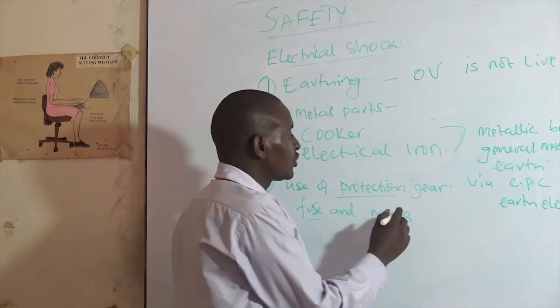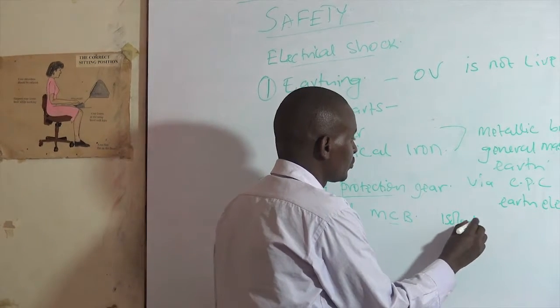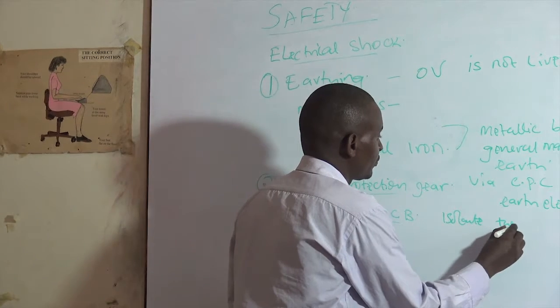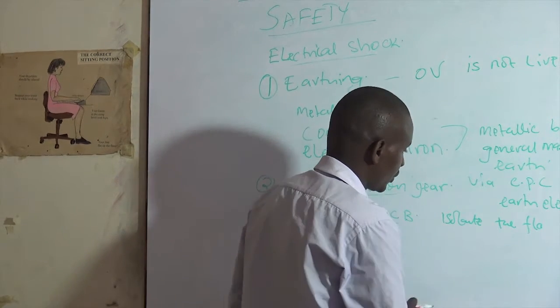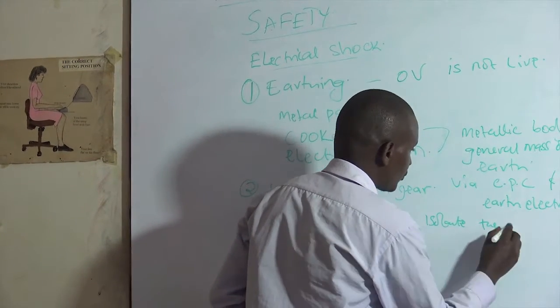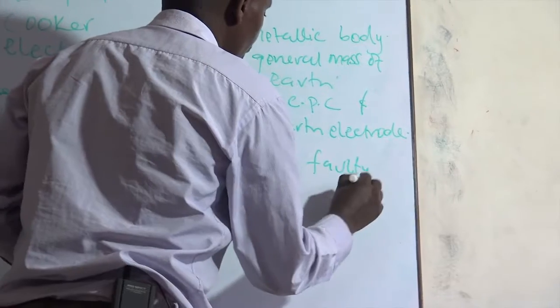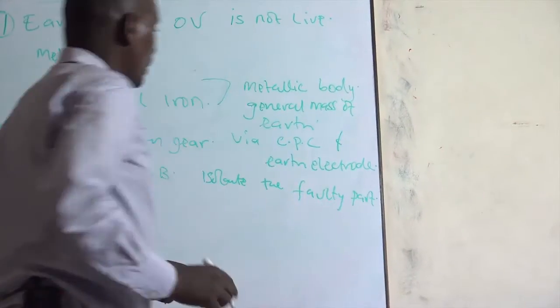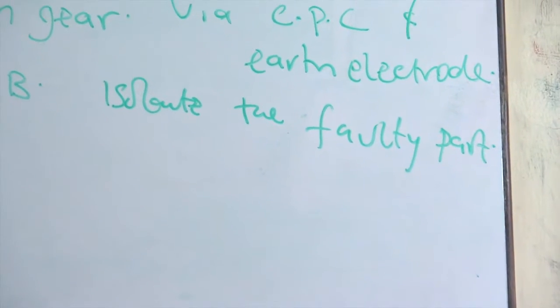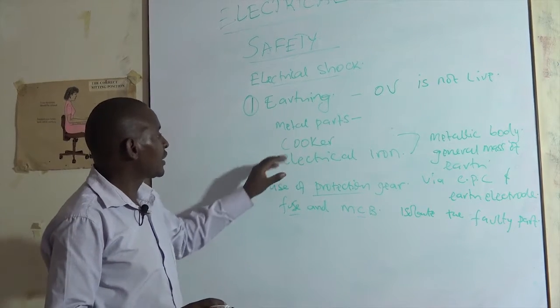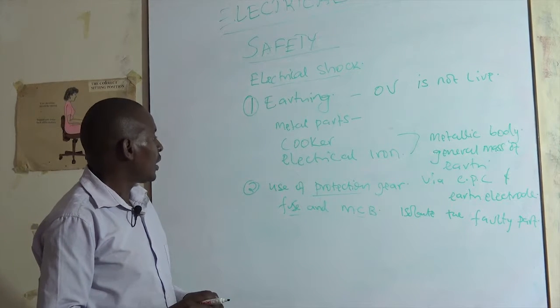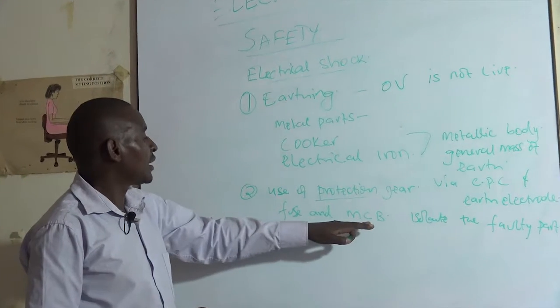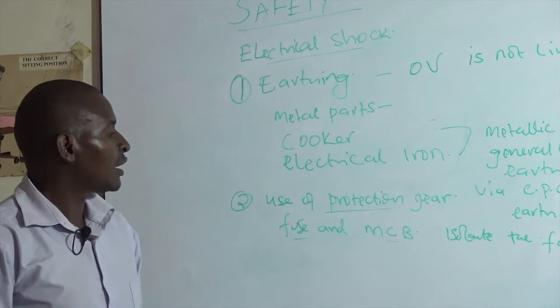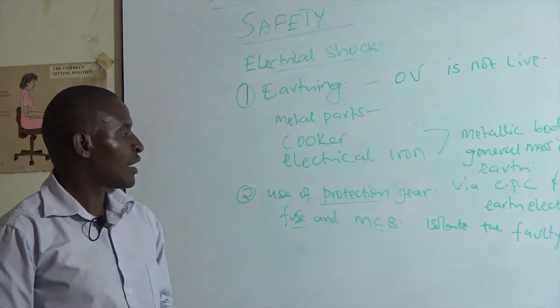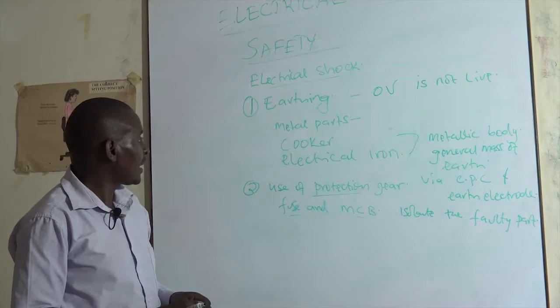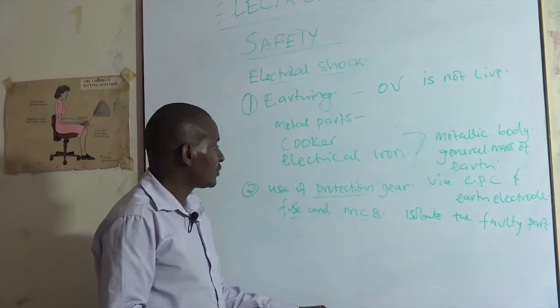And once it operates, it should isolate the faulty part, such that you don't get the metallic casing or the metallic framework being electrically charged, because the protection has operated and the MCB has isolated the faulty part, and by doing so we reduce the risk of an electric shock. And this is how the earthing should be done.